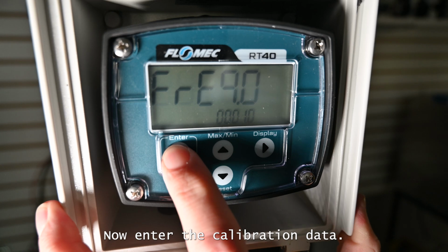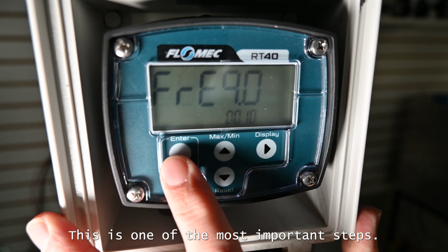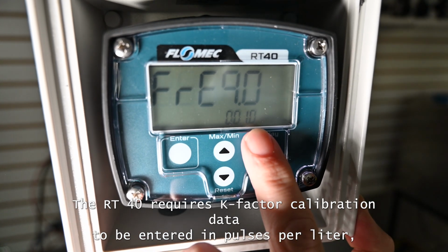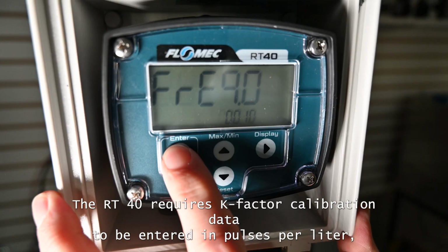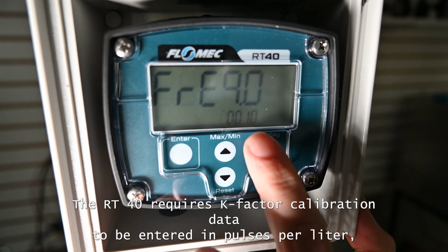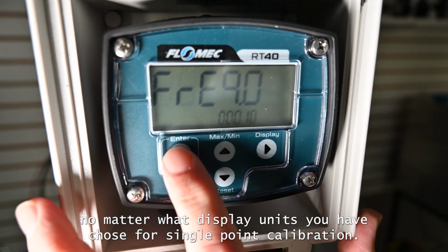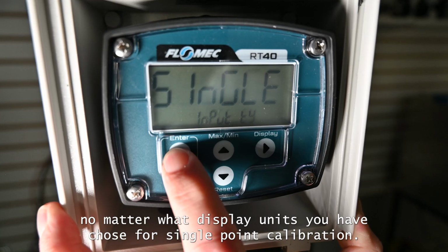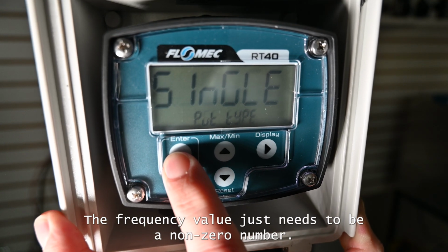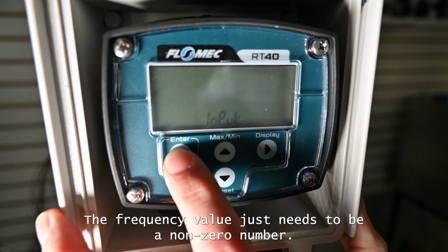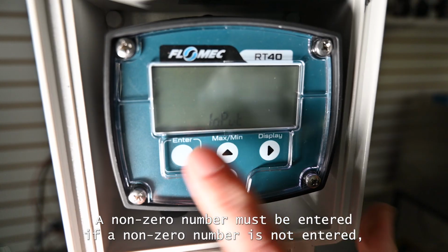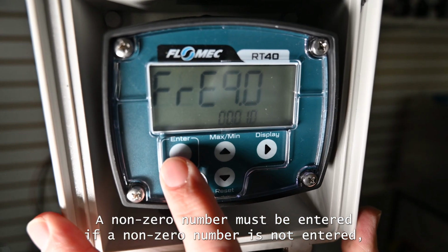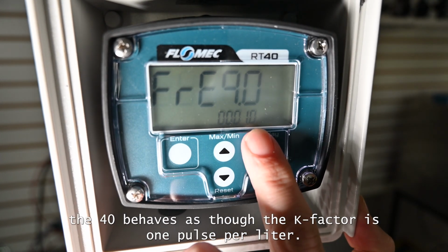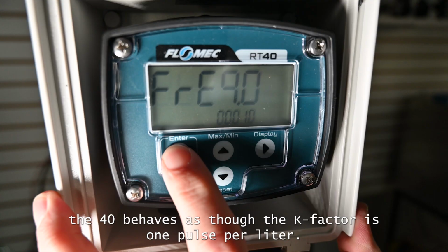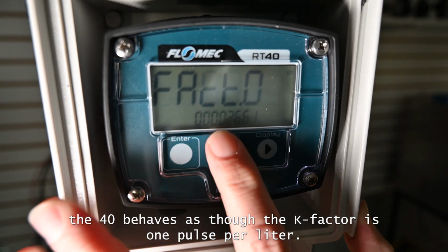Now enter the calibration data. This is one of the most important steps. The RT40 requires K-factor calibration data to be entered in pulses per liter, no matter what display units you have chosen. For single-point calibration, the frequency value just needs to be a non-zero number. A non-zero number must be entered. If a non-zero number is not entered, the RT40 behaves as though the K-factor is 1 pulse per liter.